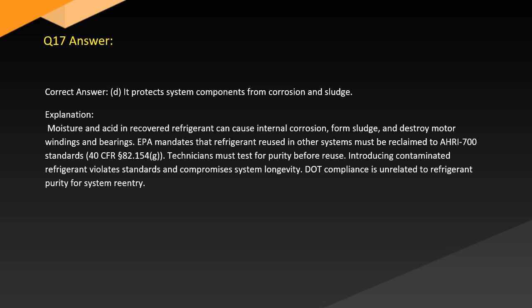Answer. Correct answer. D. It protects system components from corrosion and sludge. Explanation. Moisture and acid in recovered refrigerant can cause internal corrosion, form sludge, and destroy motor windings and bearings. EPA mandates that refrigerant reused in other systems must be reclaimed to AHRI 700 standards, 40 CFR 82.154(g). Technicians must test for purity before reuse. Introducing contaminated refrigerant violates standards and compromises system longevity. DOT compliance is unrelated to refrigerant purity for system re-entry.